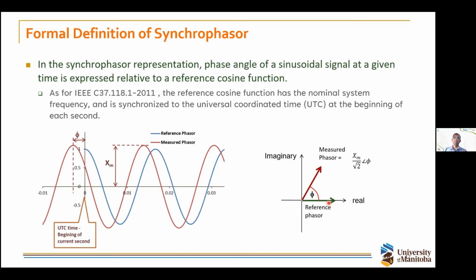Why do we need to consider this absolute time reference like UTC? That is because when you observe a wide area, measurement devices are not at the same location, they are at different places. All these modern microprocessor-based devices have an internal clock, but that internal clock is not always synchronized with the universal UTC. If it is not synchronized, they will have different times. Even if you synchronize them at the very beginning, these clocks start drifting with time, and after a while they will have different times in their internal clocks.